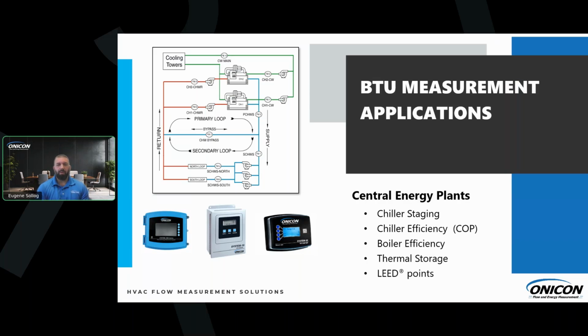When we're talking about billing on a high level for energy plants, you're billing tens of thousands of BTUs per day. So you really want that accurate flow measurement system with an accurate BTU meter. And it's good to have it all under one roof. We're taking control of that with one of our BTU meters and our flow meter. Everything is paired and calibrated together here at ONICON.